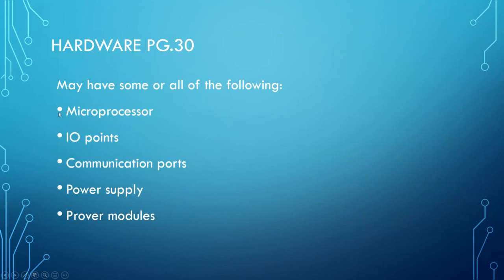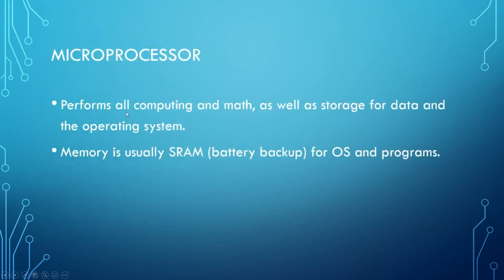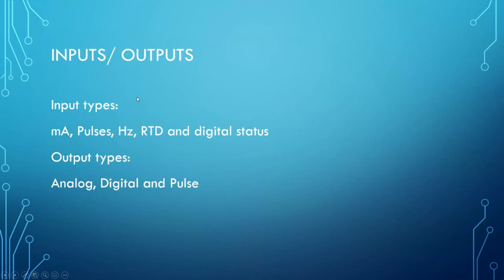Components found in flow computers include a microprocessor to perform all computing, math, and data storage with the operating system; memory (typically RAM) holding the operating system and programs; and inputs and outputs that vary by design. Typical inputs include milliamp inputs, pulse inputs from turbine meters, frequency inputs, RTD, and discrete inputs. Outputs include analog, digital, and pulse outputs — a multitude of possibilities depending on the particular flow computer style.